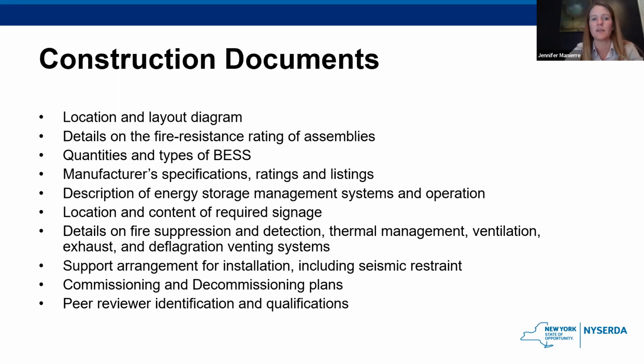Location and layout diagram, details of all the fire resistance ratings of the assemblies. I'm not going to read through every single one of these. Most of them are fairly self-explanatory. Basically, you're going to want to see all the different fire safety things that are included, commissioning and decommissioning plans. That's pretty important. You want to make sure that the system is going to be tested properly before it's plugged in and turned on, right? And decommissioning in particular is really important, to make sure that there's a plan for removing the batteries safely at the end of their useful life, or perhaps after an incident that renders some of them non-functioning anymore.